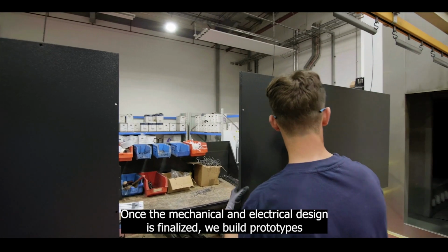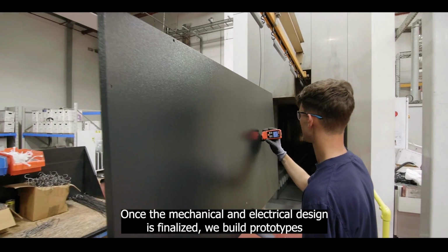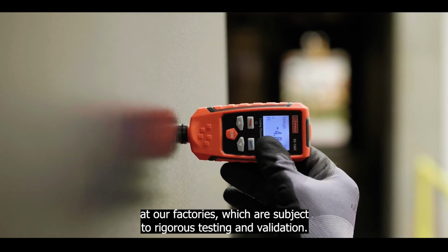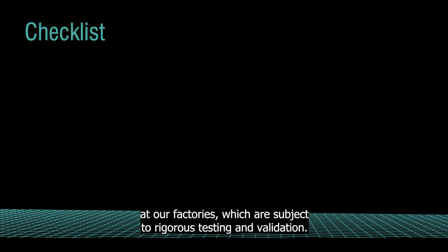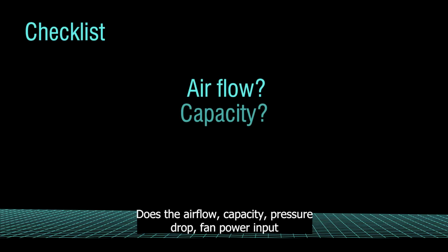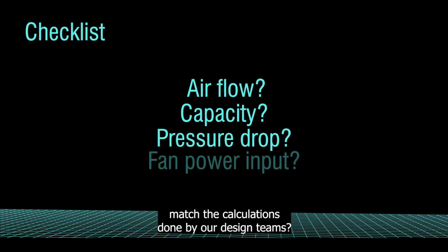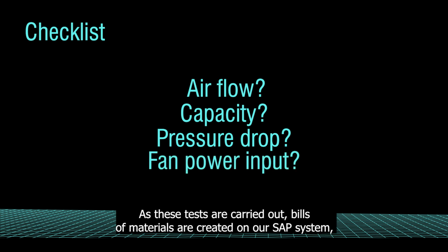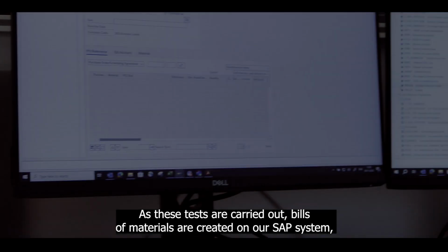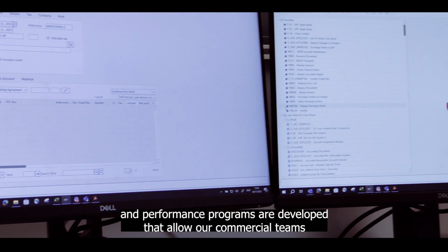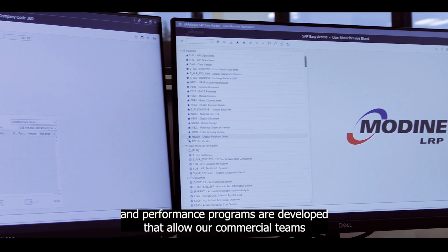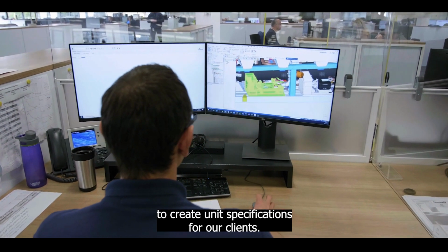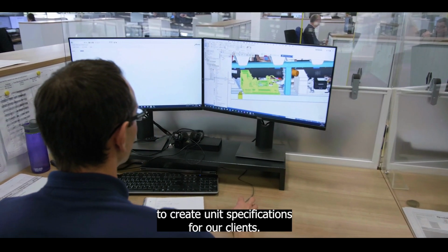Once the mechanical and electrical design is finalised, we build prototypes at our factories, which are subject to rigorous testing and validation. Does the airflow, capacity, pressure drop, and fan power input match the calculations done by our design teams? As these tests are carried out, bills of material are created on our SAP system, and performance programs are developed that allow our commercial teams to create unit specifications for our clients.